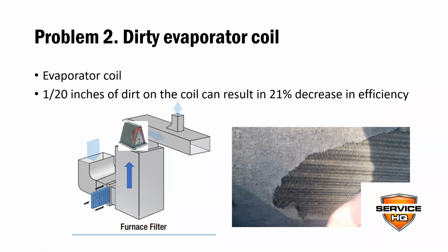The second problem that it alerts us to when we check those superheat and subcooling and the pressures and temperatures is a possible dirty evaporator coil. Once we get the story of what's happening by testing those things, it'll let us know if there's any dirt on this evaporator coil. This is what the coil should look like, and you can see this layer of dirt that happens, especially if it has not been filtered properly. After years of operation, dust and dirt will pass through that filter, especially the bad filters that don't do much, and it coats this coil. 1/20th of an inch of dirt on this coil can result in a 21% decrease in efficiency.